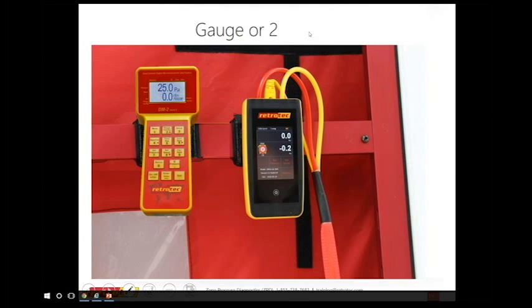Actually, yeah, I like using 1 gauge. However, in many cases, I do teach using 2 gauges, simply because I like having that automatic control over the fan. That way, if something happens, if things change, that fan can still maintain that 50 pascals of pressure. When we start getting into more advanced diagnostics, we're going to be changing things around and always having to run back and readjust and make sure that we're still at 50 after we've made some changes can really add a lot of time and be inconvenient. Exactly. That's really the big one.